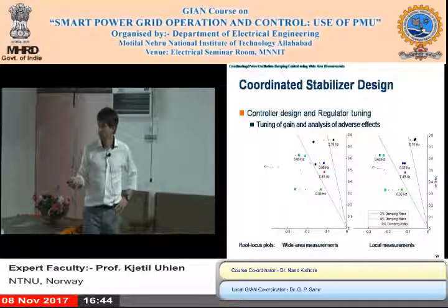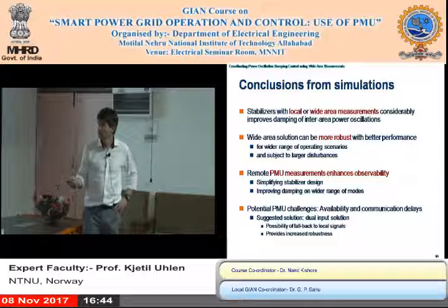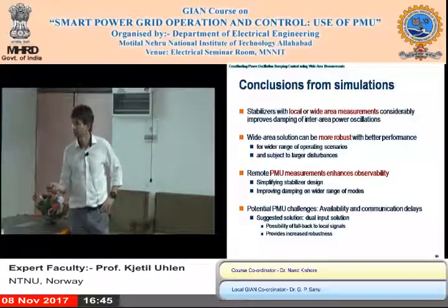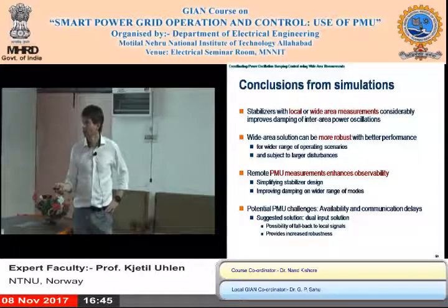Main conclusion: we thought we could conclude that a wide area solution could be more robust than local measurements, mostly because PMU measurement enhances the observability of the modes in question. And then, of course, there were some questions that we had.